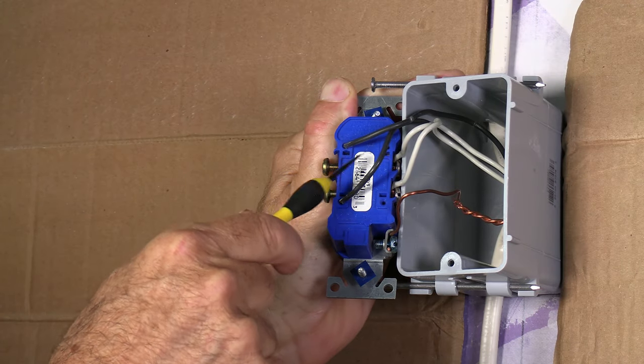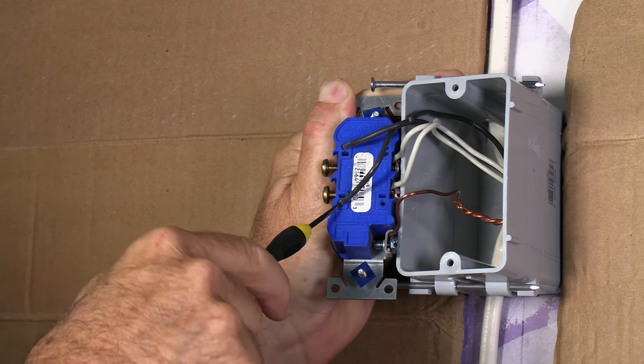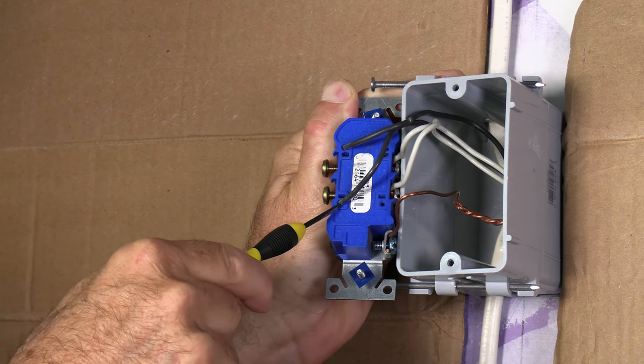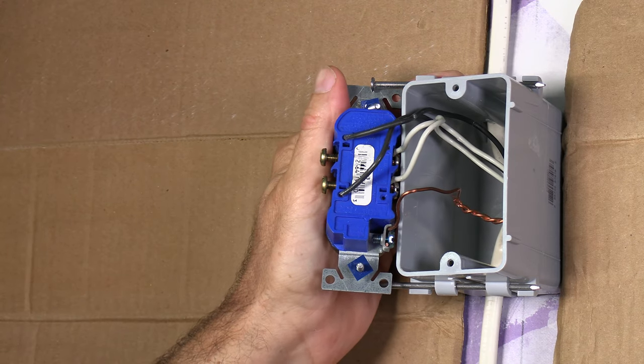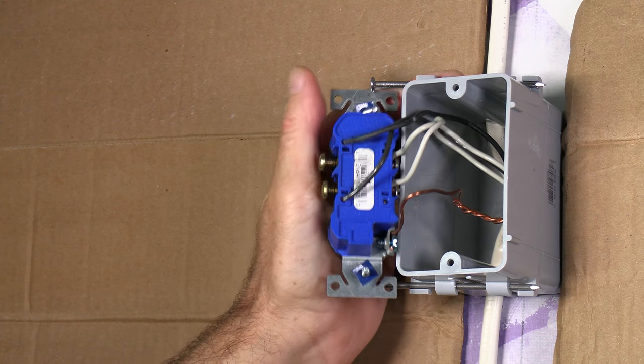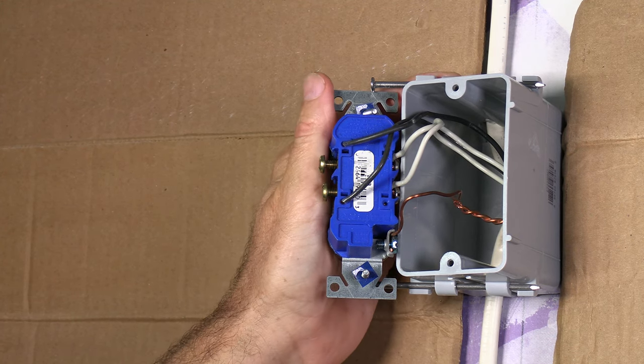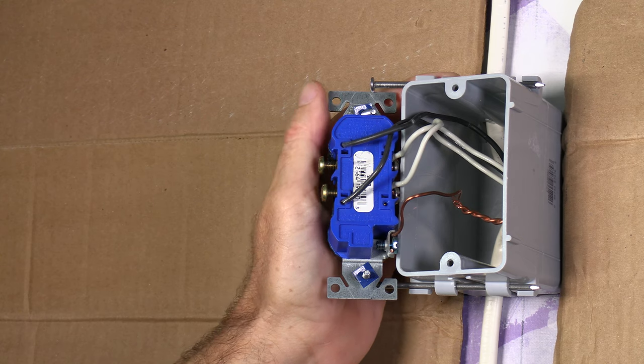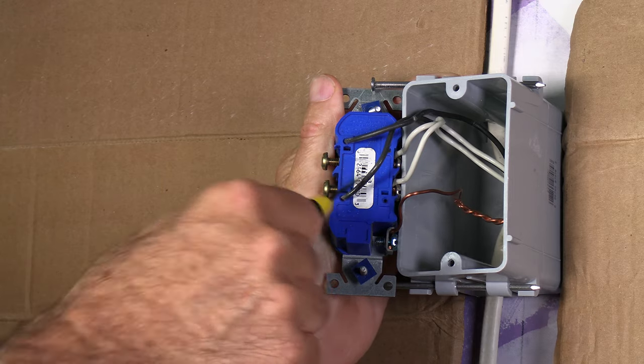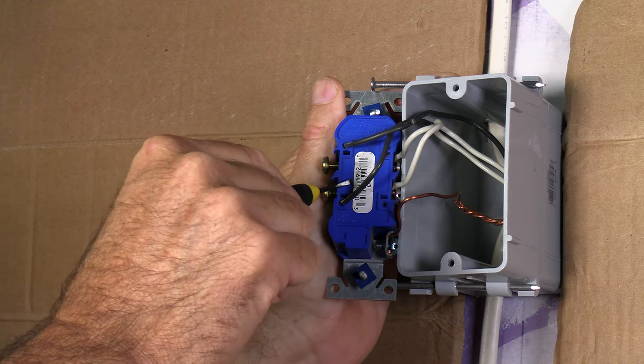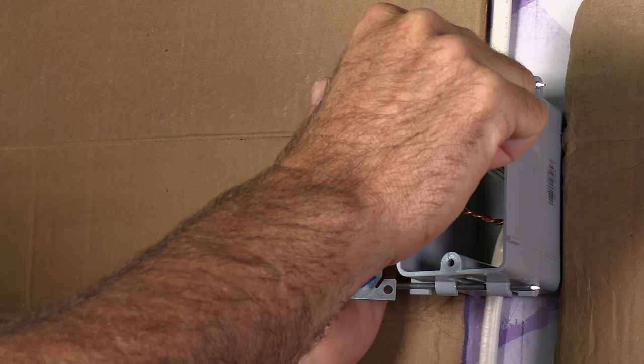Okay. Some of these plugs are going to have an area in the back here where you can stab your wire through and it'll grip it. I personally do not like to use this. I had an episode one time where I was helping a friend track down a problem where the plug was intermittent. She plugged the vacuum cleaner in and it would work sometimes and not others. So I looked around the house to the plugs that she was using and found when I took this one out. Well, not this one, but when I took her plug out, the wire was barbecued all the way to the back of the box.